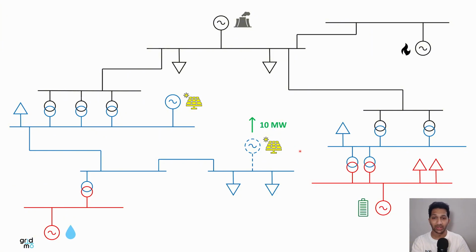To do this, we will need to ensure we are still maintaining the balance between load and generation in the network. This is to make sure our network still represents the scenario we wish to study, including the same load demand, total generation, and power flows across major interconnectors. Also, one assumption we will make is that there will be negligible load growth between the present day and the future scenario we are modeling, which is just 1 year into the future. Given that we won't be looking to adjust the load demand, let's adjust the generation in the network instead.